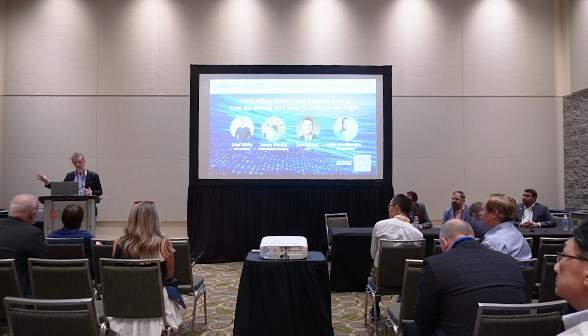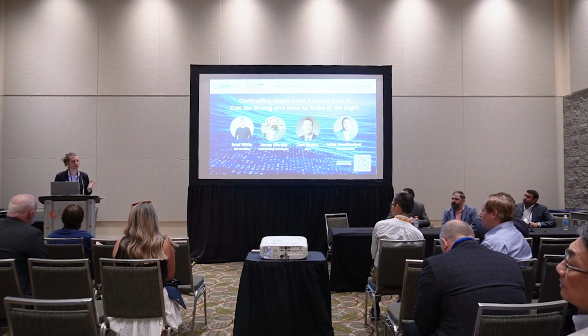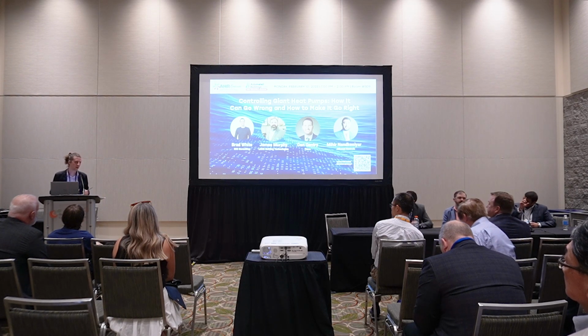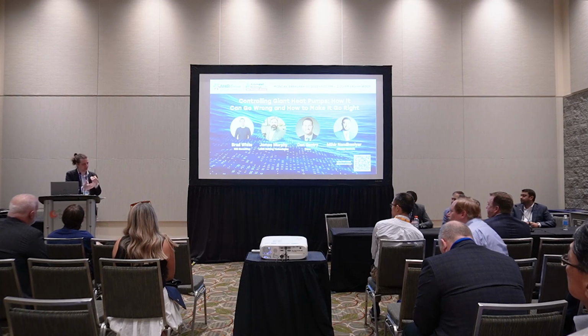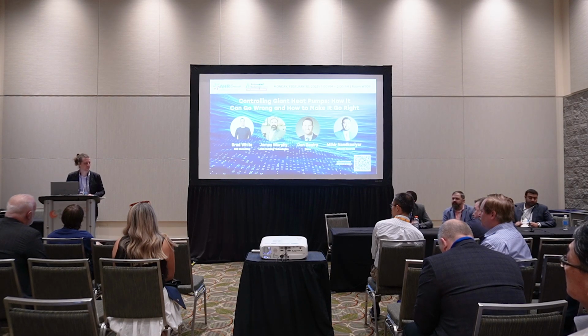And so you can't assume that the sizing is going to be correct. Even if you use some industry standard tools, you will get sizes that are way too big. Another lesson we take with all our heat pump designs is we try to use data because we do a lot of retrofits. So before we even do the project, we're looking at what the existing heat loads in the building look like. We're looking at what kind of temperatures it needs, and then using that to help inform the size and type of system that we recommend.